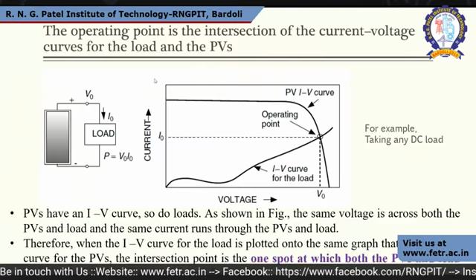So if you take an example of DC load, the first is the resistive load. If you connect the resistive load with the PV panel, then the first concept one must know is the operating point. So this is the operating point. Visually, anyone can check what the operating point is, but it is a point at which the IV curve of PV is intersecting the IV curve of the load.